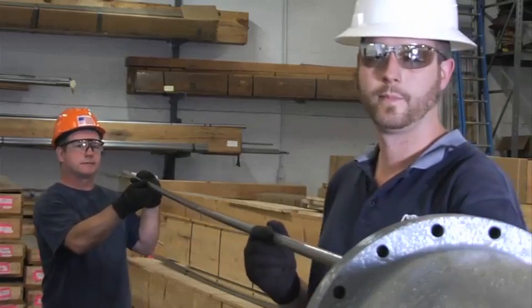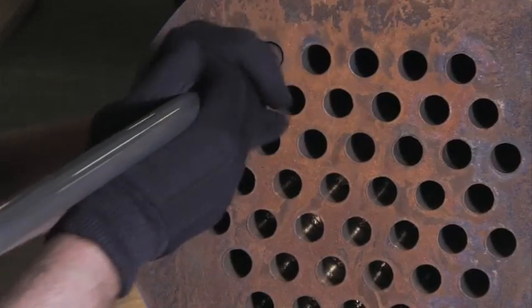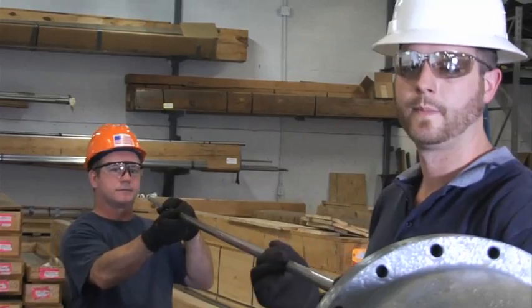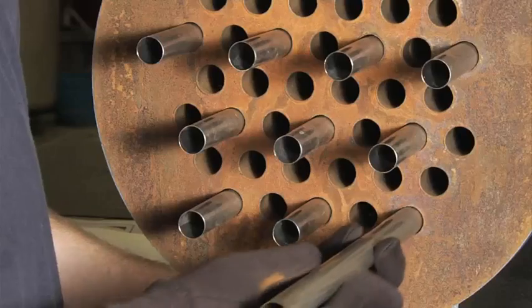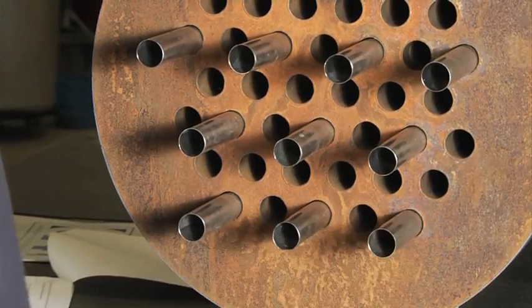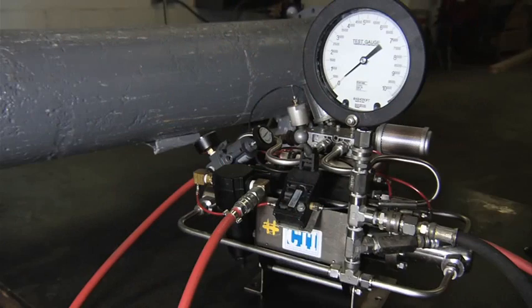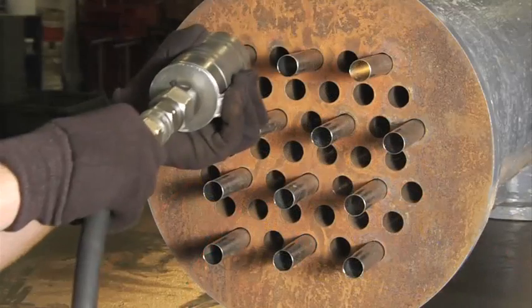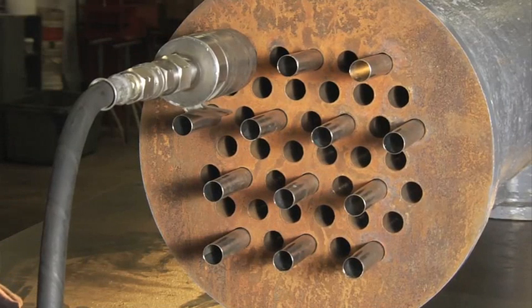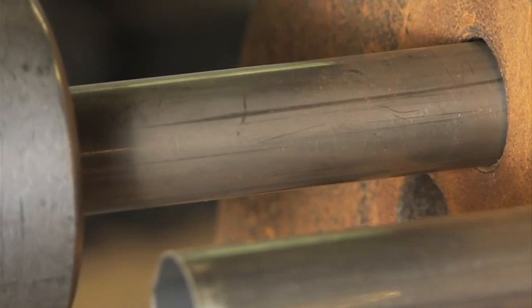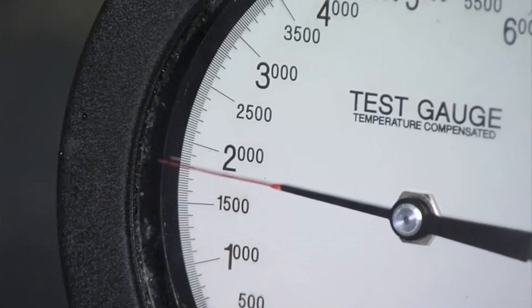CTI has also developed a full length tube liner for those heat exchangers with tubes suffering full length problems. Once the tube IDs have been thoroughly cleaned, thin-walled alloy liners are installed into the damaged tubes. A sealing chuck that is connected to the CTI hydraulic liner pump is attached to one end, while a bleed chuck is attached to the opposite end. The liner is filled with water, the air released, and the pump is engaged.